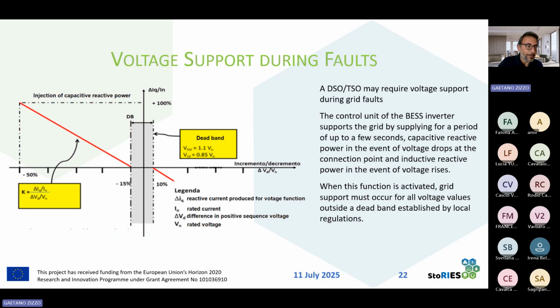This function allows the storage system to contrast the voltage reduction. If it does, it can be used for helping all the other generators in the same area, close to the node to which it is connected. So in this case, the storage system is used for supporting voltage in an area of the grid, helping to maintain the connection of the other devices closer to that node. On the contrary, if the voltage in that node increases over 110% of the rated voltage, the storage system is controlled for increasing the absorption of inductive reactive power. In this way, it behaves like a reactor connected to that node, helping in reducing the voltage of the node.